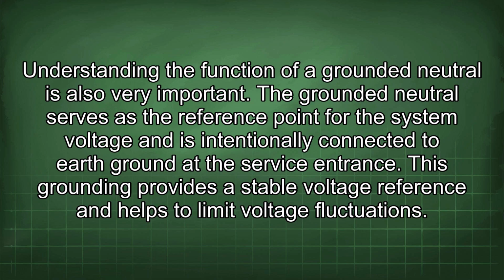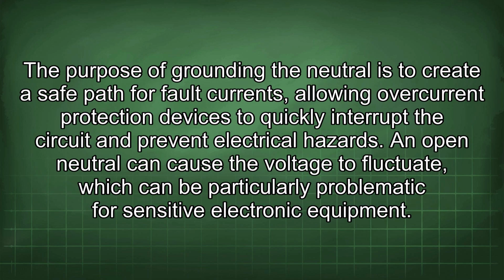Understanding the function of a grounded neutral is also very important. The grounded neutral serves as the reference point for the system voltage and is intentionally connected to earth ground at the service entrance. This grounding provides a stable voltage reference and helps to limit voltage fluctuations. The purpose of grounding the neutral is to create a safe path for fault currents, allowing overcurrent protection devices to quickly interrupt the circuit and prevent electrical hazards.